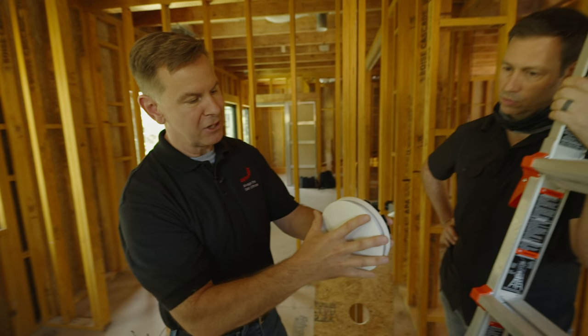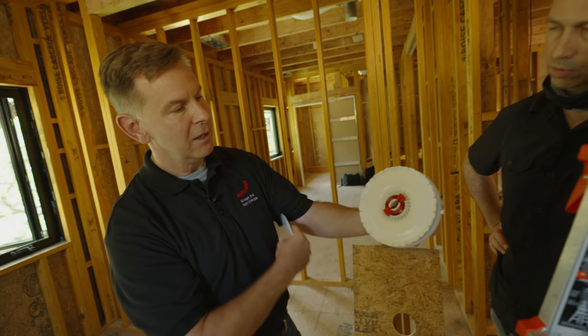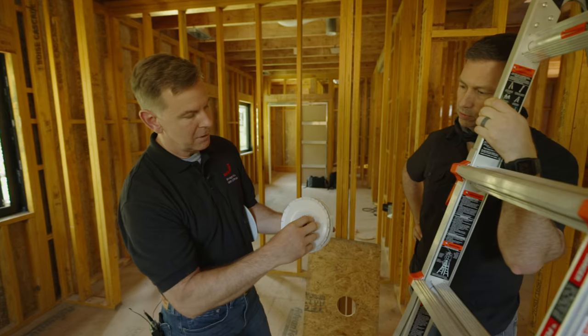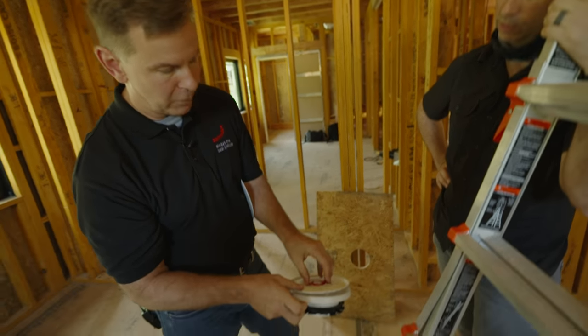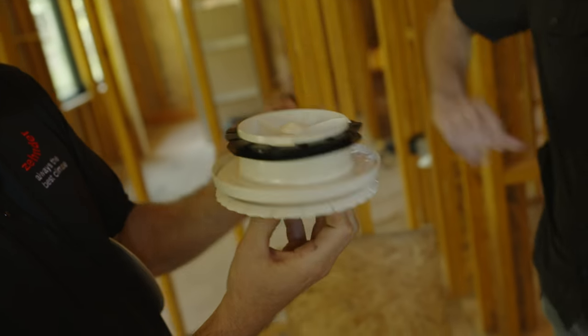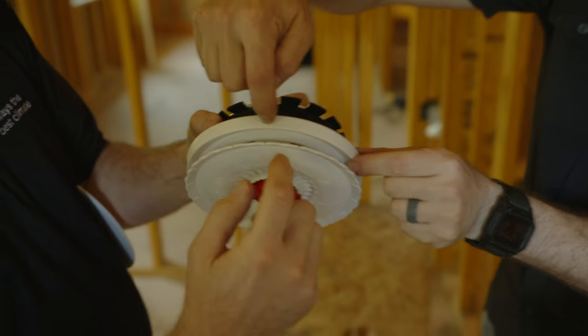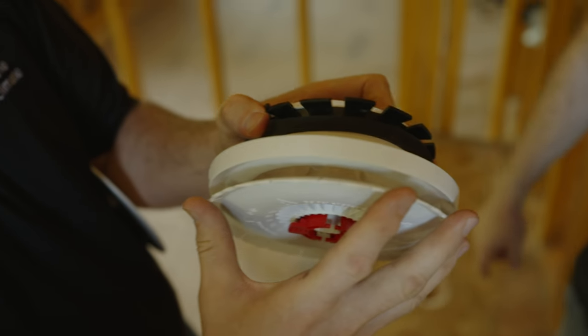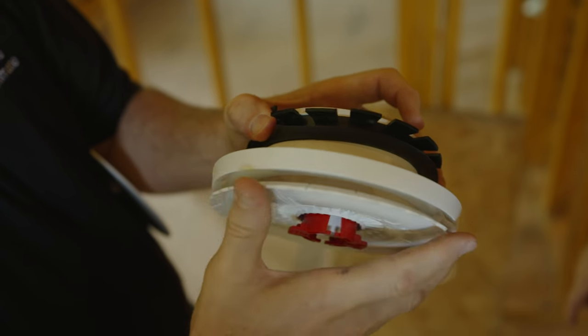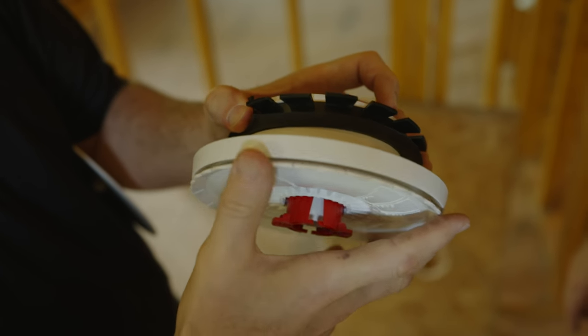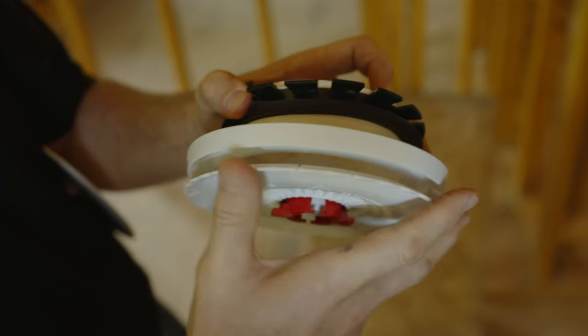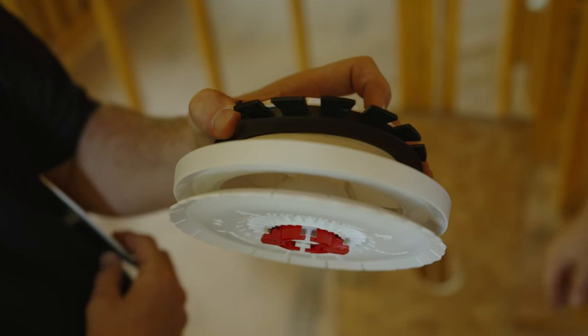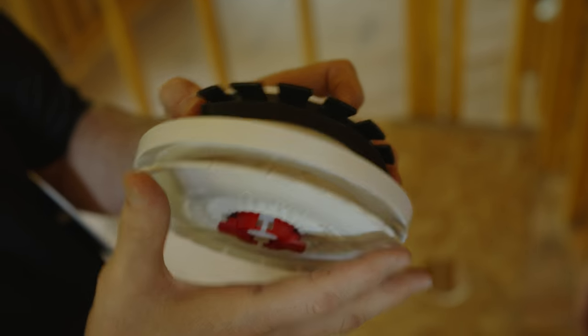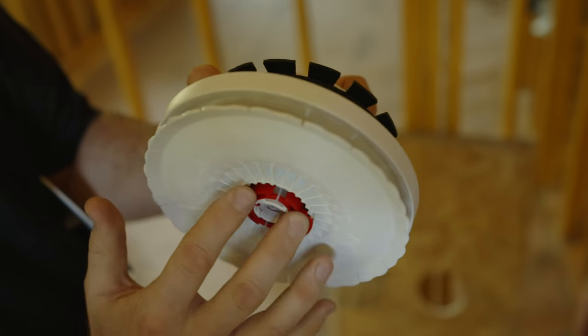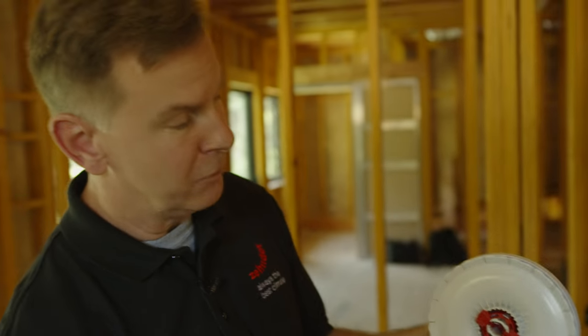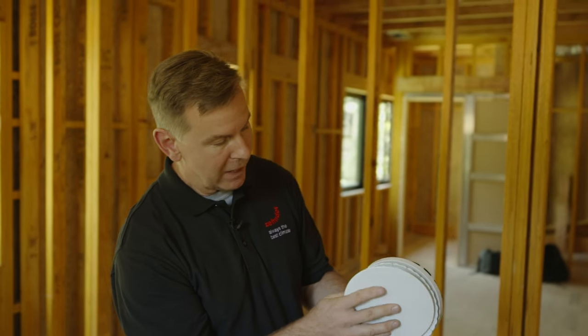So we give this cover a little turn and pull it off. What we see is a locking mechanism - if we unlock that, we can adjust it. Keep your eyes tuned right here: this part is fixed and this part moves. You'll see as Chris turns it, our gap closes down as we turn it clockwise. If we want to open it up during commissioning and get more airflow, we back it off counterclockwise. Once we figure out where we need to be, we push this in, lock it in place, and it's tamper proof. Then get the cover back on.